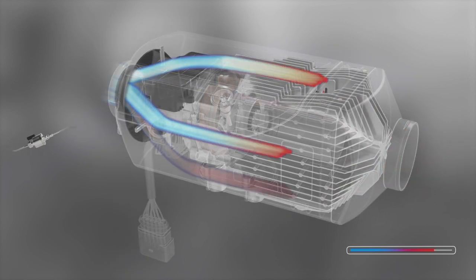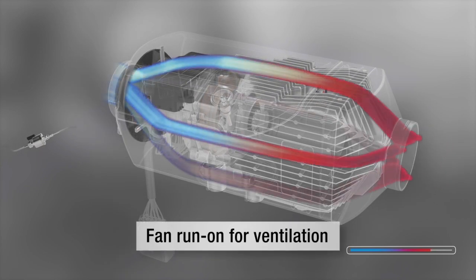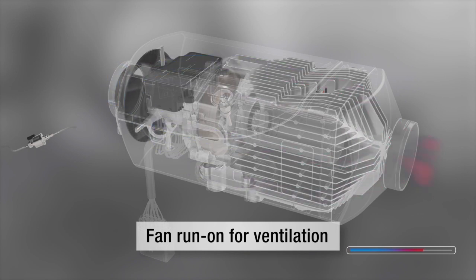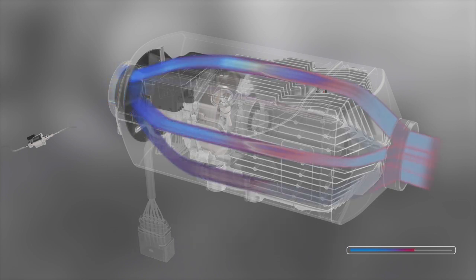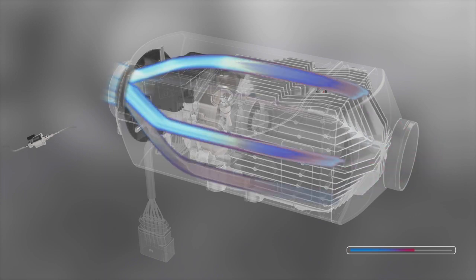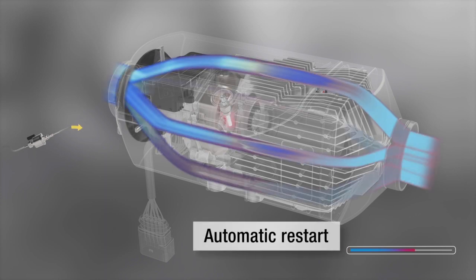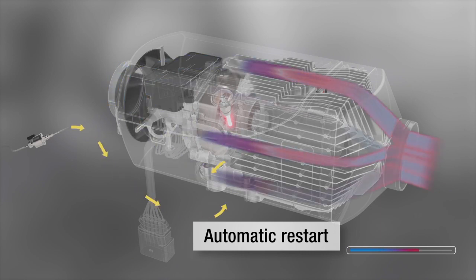The fan continues to run for a few minutes. The control unit then switches the fan to ventilate so that the interior air continues to flow around the temperature sensor. If the interior temperature falls below the specified set point, the temperature sensor detects this. The heater restarts, but this time at a lower power level.